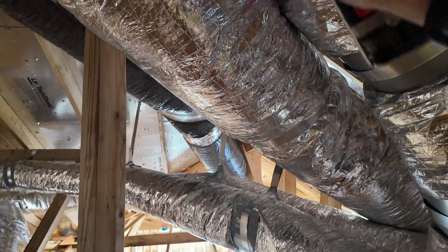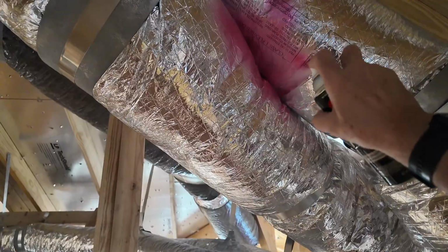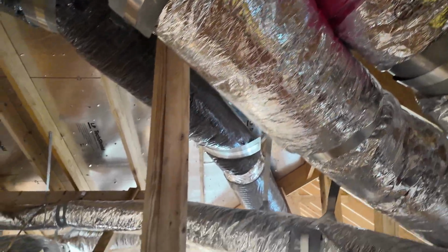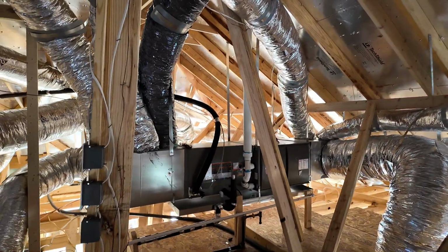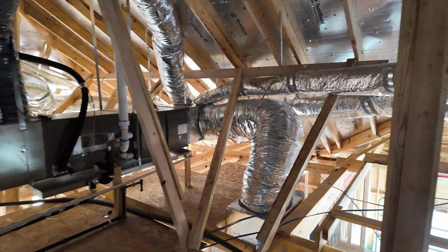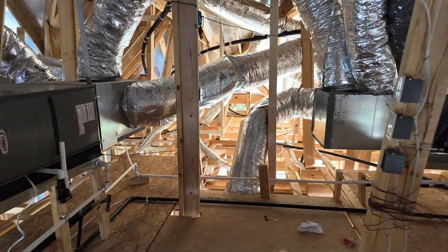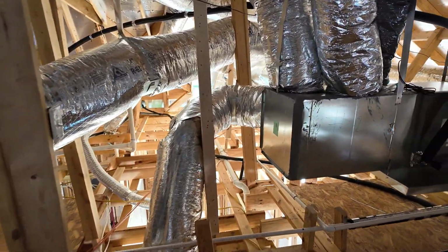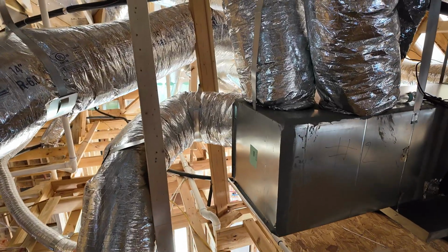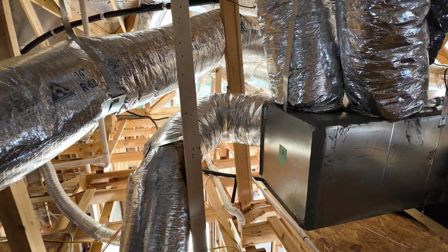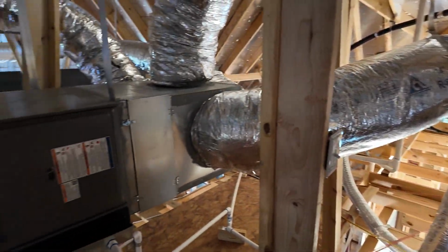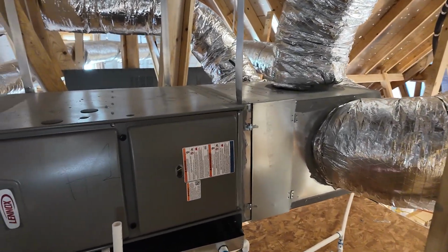But if your air duct is rubbing against other air duct, well then that's going to cause condensation. And the condensation is going to fall down to your attic floor. And then after it goes down to your attic floor, it's going to go down to the ceiling below. That's what it's not supposed to be doing. It's not supposed to be making bends like that. Okay, so I got bends. I don't have too much in the way of sag.